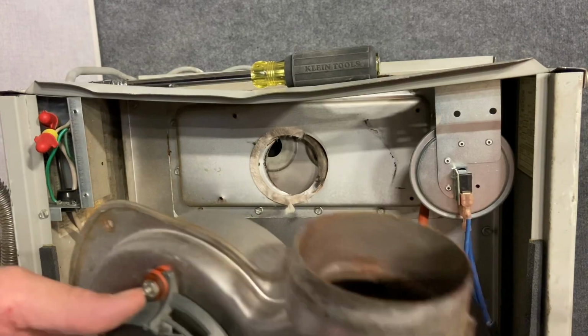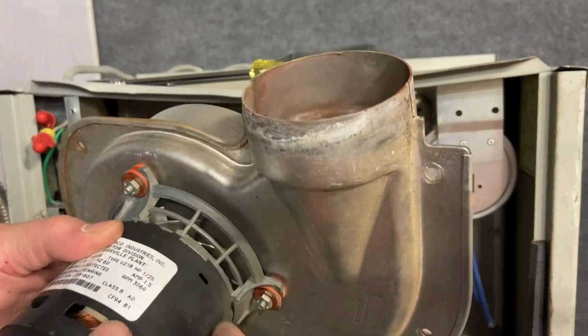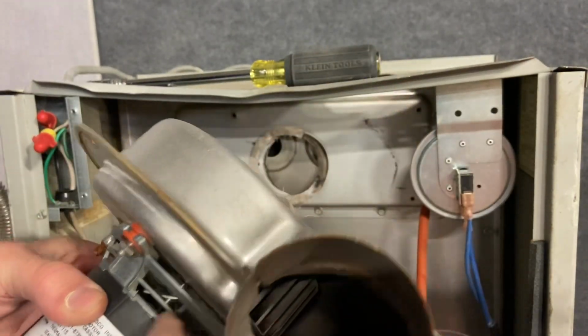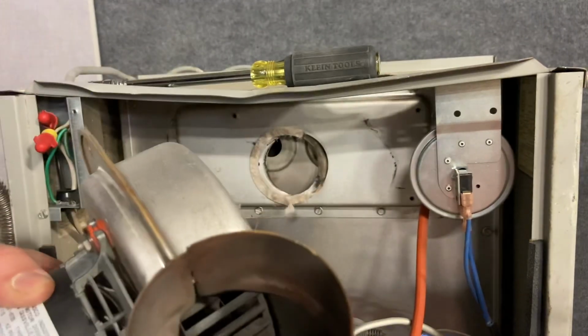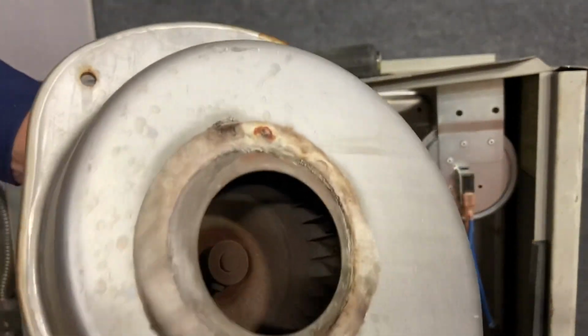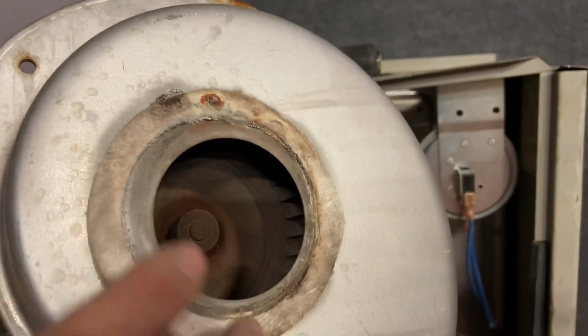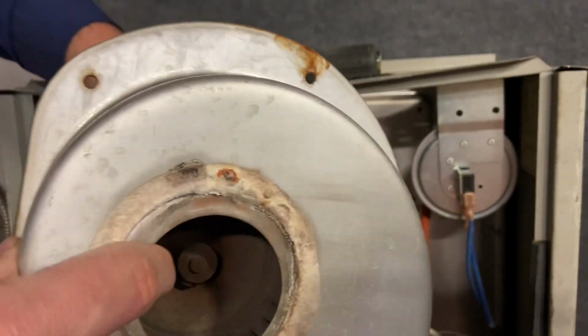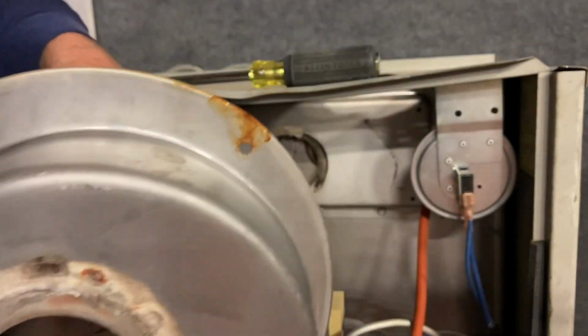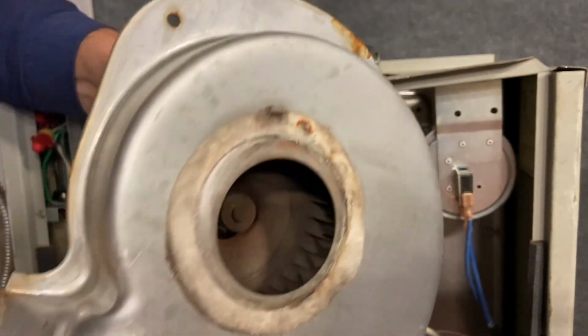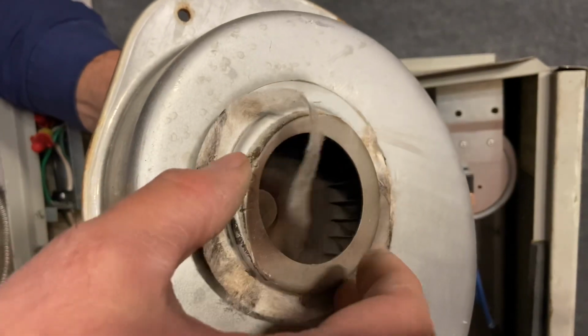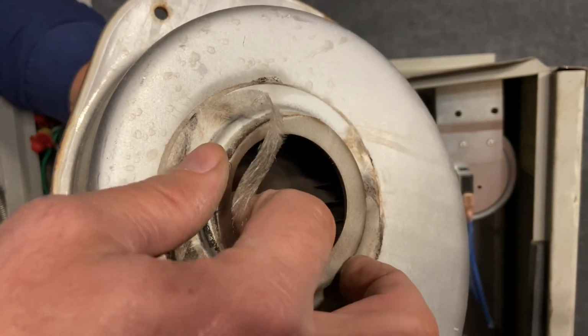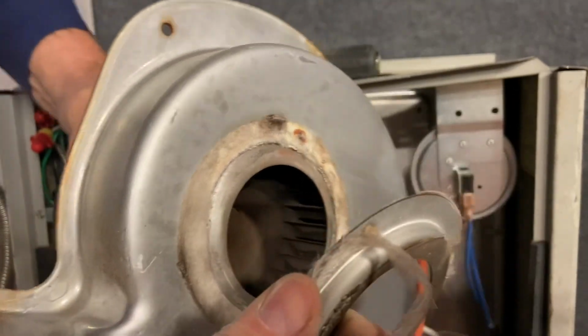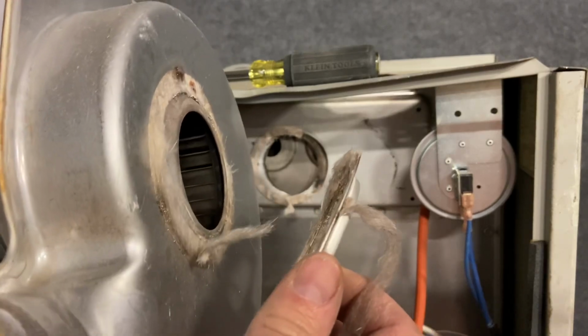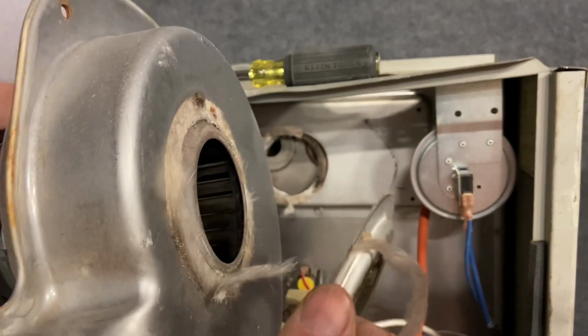We order it back from the manufacturer. Even though you could theoretically order just this motor, trying to replace it inside of this housing is not an easy thing to do. Also, very specifically, this hole on the sides of here is for a very tight tolerance of how much air it can pull in. And when I took this motor off, there's also this little bracket fell out. This bracket is an adapter on here so that it gives a even more precise hole. So if I were to put this back together and not have this bracket in there, I could change the airflow, which would change the air-fuel mixture.